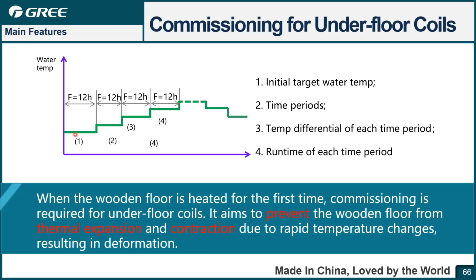So at the beginning, the heating temperature is very low, and gradually increases to another stage, and the next stage, and the next stage, and then cools down gradually, so that the floor can become accustomed to the temperature change from the floor heating. You can set the initial target water temperature, time period, temperature differential for each stage, and the running time for each period. So this commissioning function is very useful for floor heating projects.